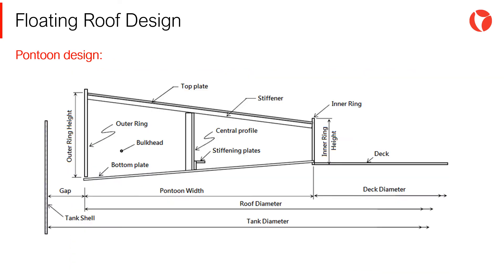The pontoon is the element that provides buoyancy to the floating roof. It is a box formed mainly of five plates: a top plate, a bottom plate, two rings — inner and outer — and a series of radial brackets. The dimensions of the pontoon, width and height, vary depending on the buoyancy requirements and the tank dimensions.